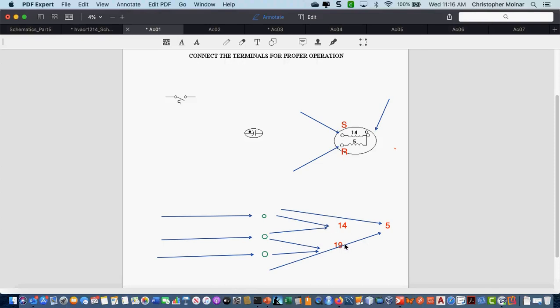Okay, so when I look at these resistance readings, I know that common is not one of these two terminals. It's not one of the bottom two terminals. Because I'm going from start to run as my highest resistance reading, since I'm taking both windings together. So I can tell you right now, these two terminals are start and run.